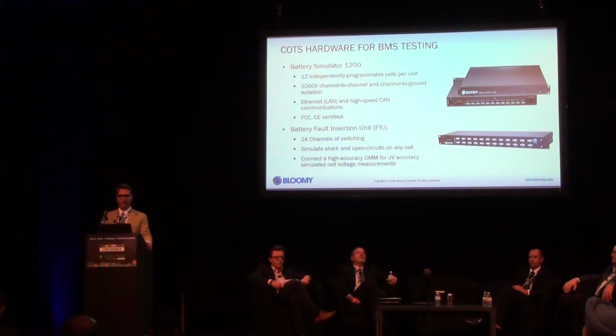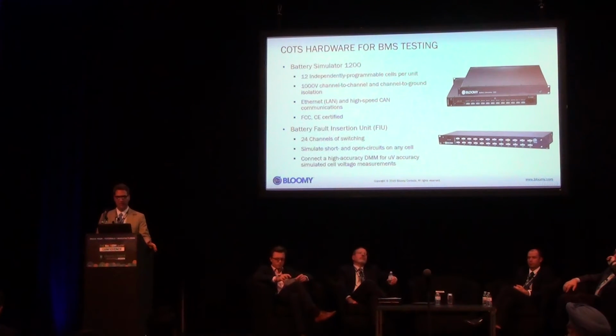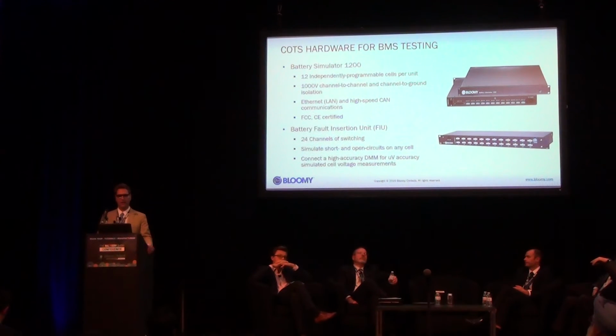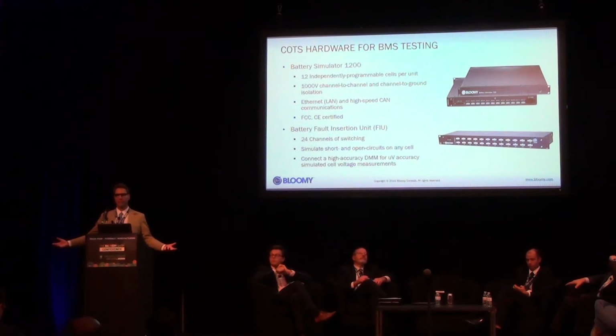Commercial off-the-shelf hardware, including specialized hardware that Bloomy has that is commercial off-the-shelf, designed specifically for these unique challenges of BMS testing. This includes the Battery Simulator 1200, which has 12 independently programmable cells that sink and source current under the BMS's control, helping you test cell balancing as well as various faults. Additionally, 1,000 volts of channel-to-channel and channel-to-ground isolation allows you to connect many of these in series to simulate a larger pack.